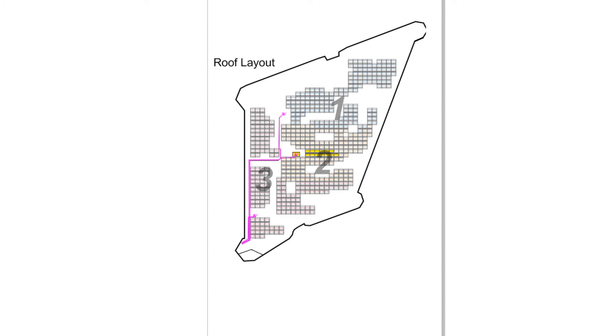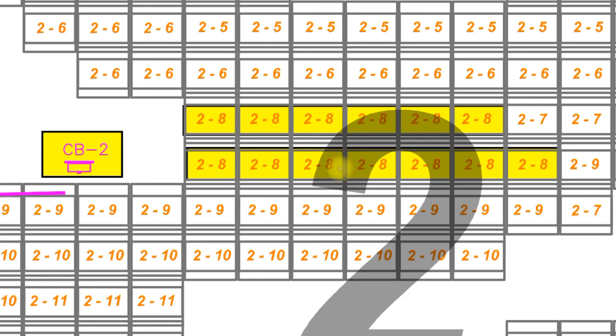Zoom in to find the location of panels connected in series as string 8 in combiner box 2. Look for a damaged connection or check each of the panels in the string to find which has a problem and needs replacing. Also check the fuse for string 8 in combiner box 2.